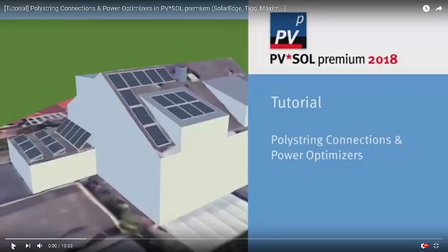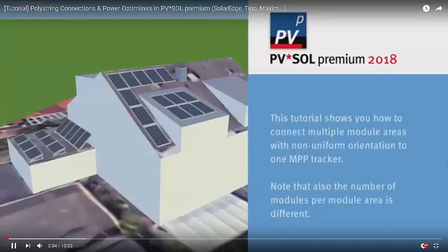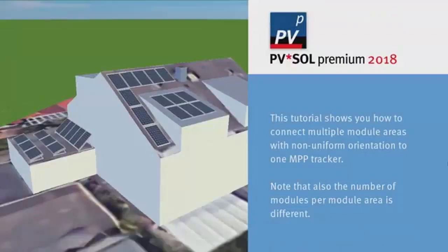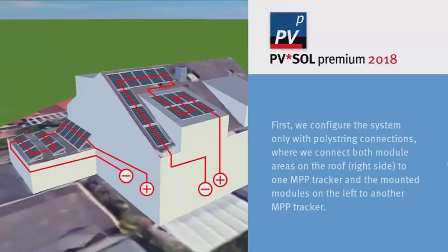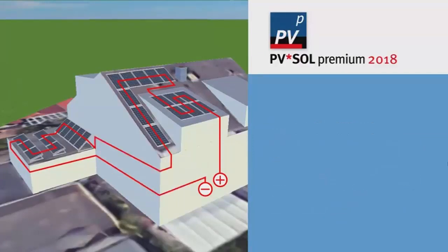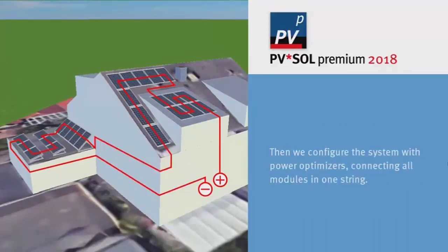So to do this, we're going to use an example building with four PV arrays facing different angles or different directions. Initially, we're going to connect all those areas up on a string inverter, which has two maximum power point trackers, which you can see illustrated in the drawing there now on screen.